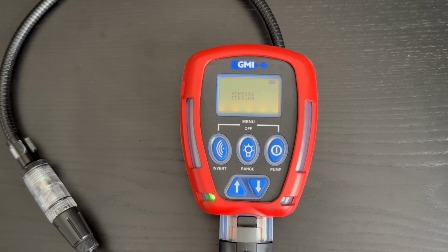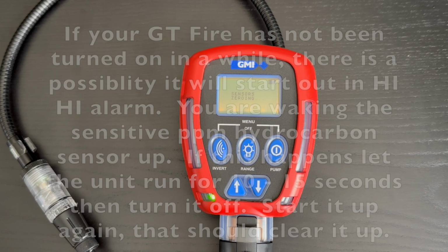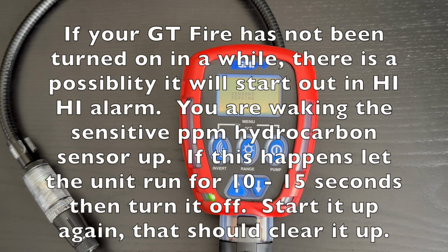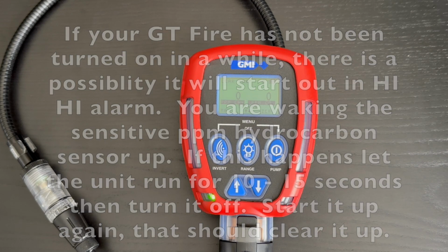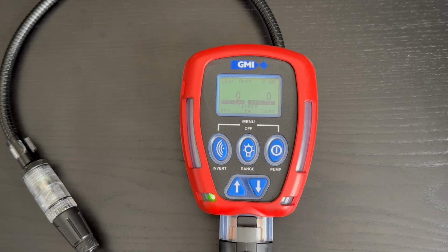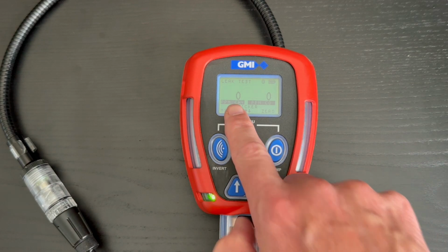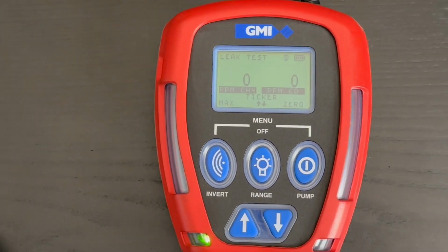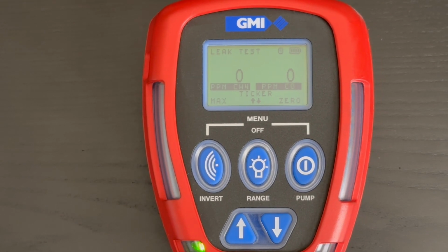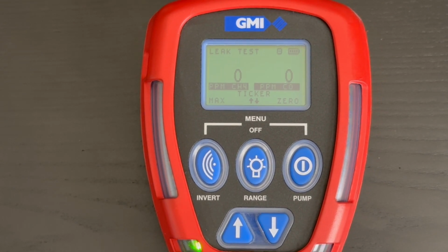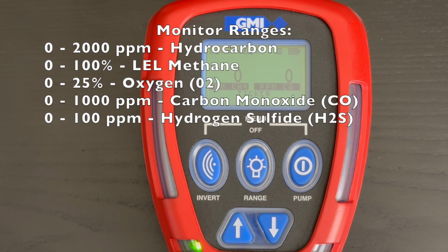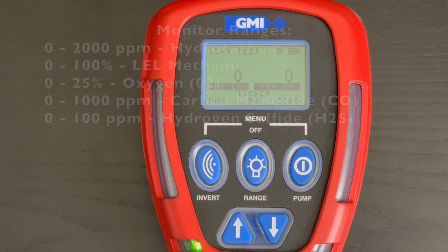In this particular instrument, it's going to go into what we call leak detection. So you'll notice you're in leak detection. If you'll look at it real close here, let me zoom in just a hair, you'll notice it's in what we call ppm hydrocarbon. So you hear the ticking. As the gas gets closer to it, the ticking will be upbeat, and you will get readings up to 2000 ppm before it auto ranges over into LEL on this particular instrument.